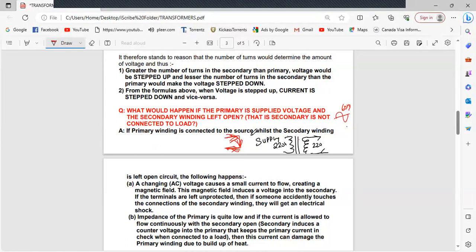Because of this increased current flow, the heat in your primary is going to be quite high. And as we know, if the operating temperature increases by 10 degrees over the normal operating temperature, your insulation life falls by 50%. Very quickly, your transformer primary will get burnt out. Is that clear now?